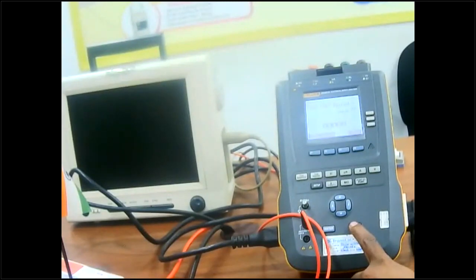Yes, okay. Now we are doing the alternate method, applying the voltage and testing the alternate equipment leakage. This is showing 165.7 microamps, which is fine, we can accept. Now we are doing the direct method on the applied parts. You can do the testing, plus test. You can see the reading, and then we can do the alternative applied parts also. Then press test.